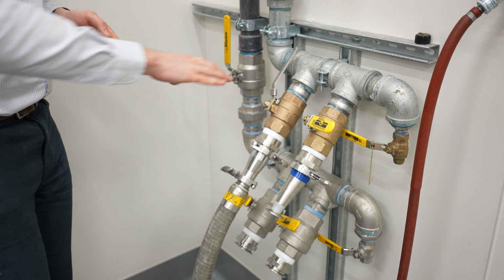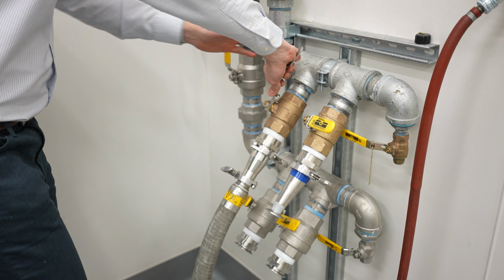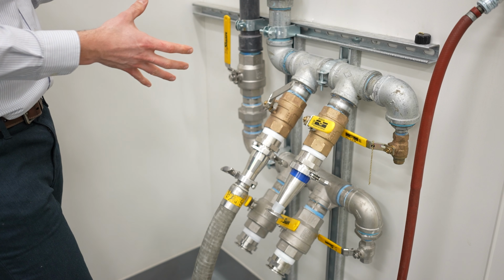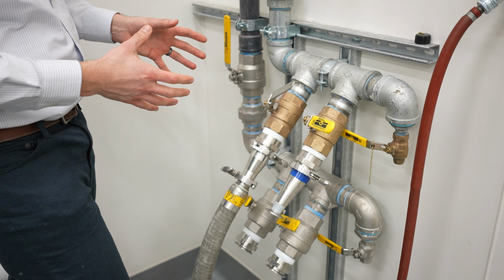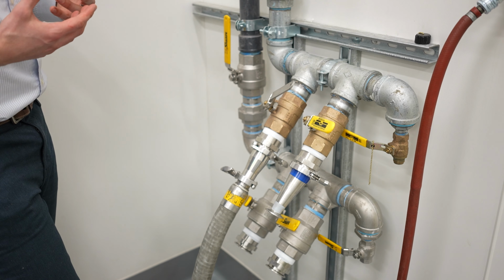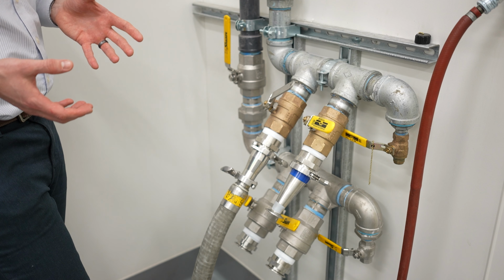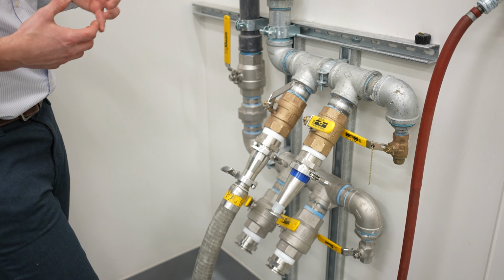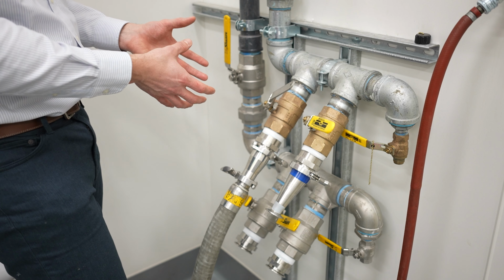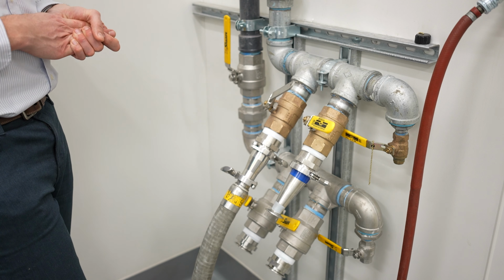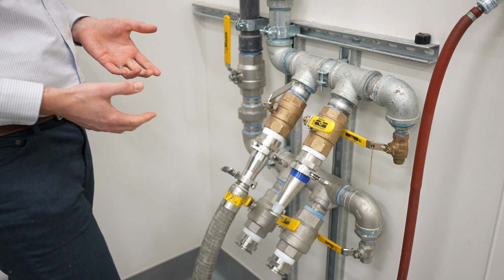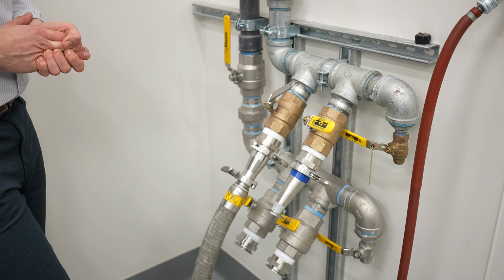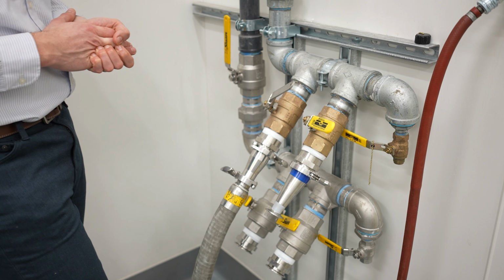So what we're gonna do is I'm gonna close this, and not all the way, but this is simulating other systems that could be attached to this water supply in your facility. They might be drawing water at the same time you're trying to fill. Maybe there's new projects you're adding to your facility where more and more systems are utilizing water from the same line, and you're getting less and less water pressure, which in turn is reducing the flow to your system and increasing those fill times for the water fill.